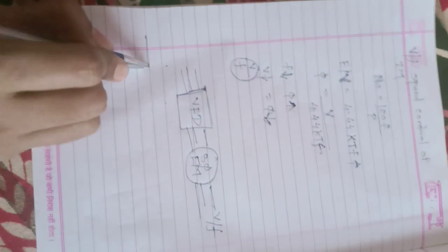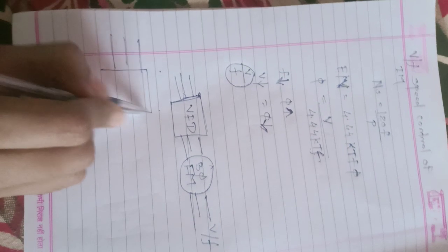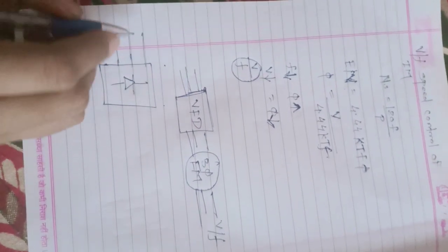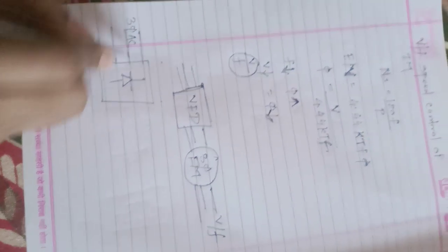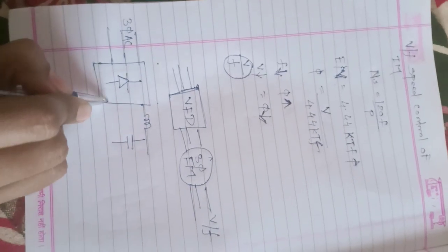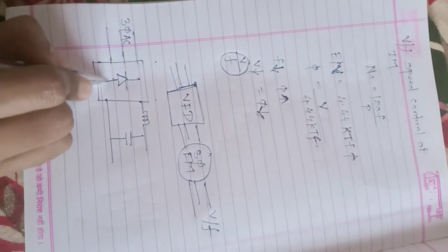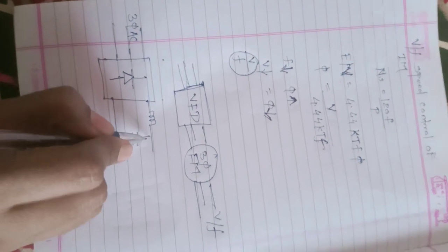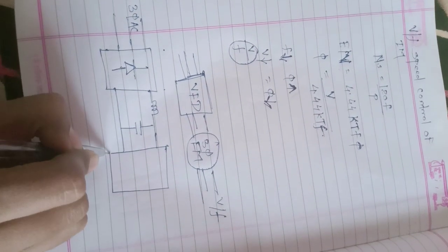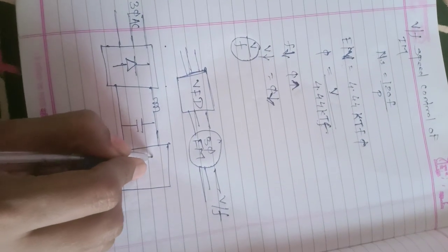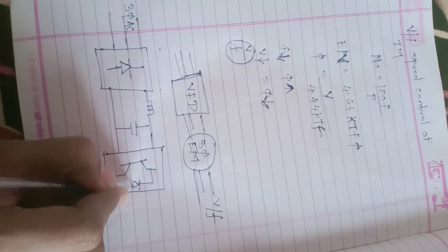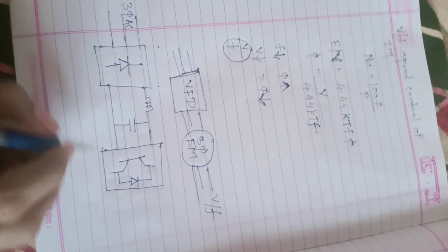First is the rectifier stage, where we give three phase AC supply to the rectifier circuitry. It is a set of 6 diodes. It converts three phase AC into DC. After that, it is connected to the filter circuit, which removes ripples contained in this DC and gives pure output to the inverter circuitry. It is also a set of 6 IGBTs or SCRs or GTOs.